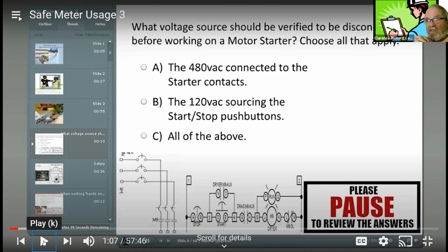480 volts is pretty easy to detect where that comes from because it goes to the top of the circuit breaker and out. Normally you've got compartments that your motor starters and circuit breakers are in. So if you flip off the main circuit breaker, you know you're cutting off the 480. You don't know all the time if you're cutting off the 120. Sometimes your 120 comes from a little transformer. In each box, they have their own transformer. And sometimes the 120 comes from your circuit breaker panel, where all of those starter coils are tied to the circuit breaker panel. They're powered up from that.